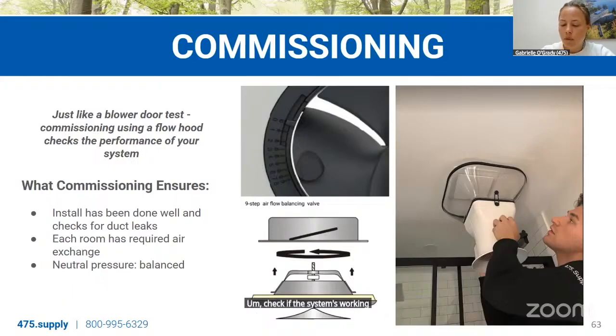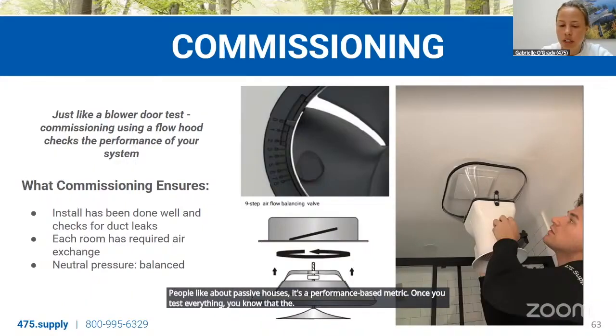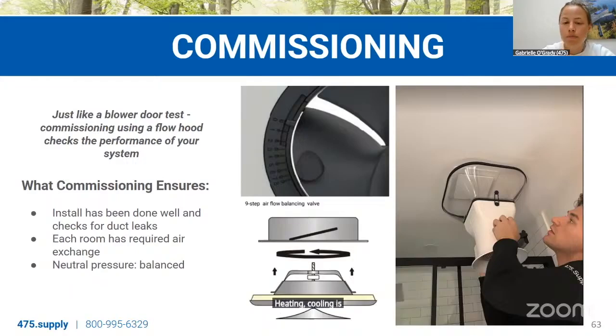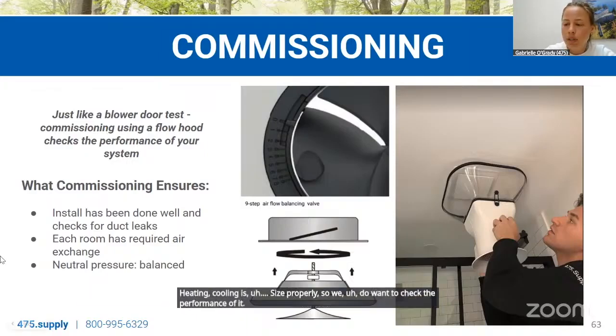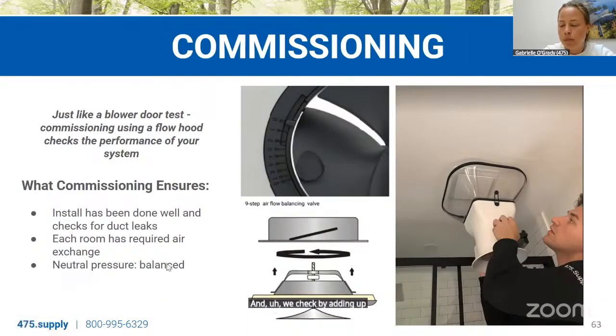One of the things that people like about passive houses is that it's a performance-based metric. Once you test everything, you know that the heating and cooling is sized properly. So we do want to check the performance of it. And we check by adding up all those supply numbers and exhaust numbers, so we can check that the home is balanced.